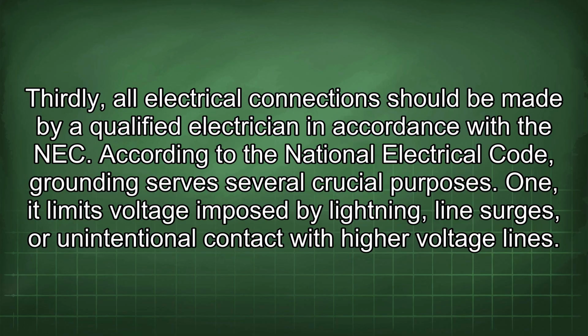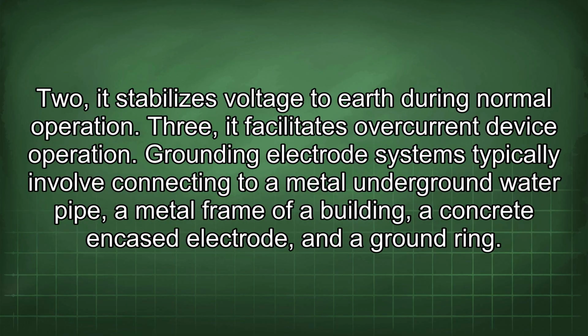According to the National Electrical Code, grounding serves several crucial purposes. 1. It limits voltage imposed by lightning, line surges, or unintentional contact with higher voltage lines. 2. It stabilizes voltage to earth during normal operation. 3. It facilitates overcurrent device operation.